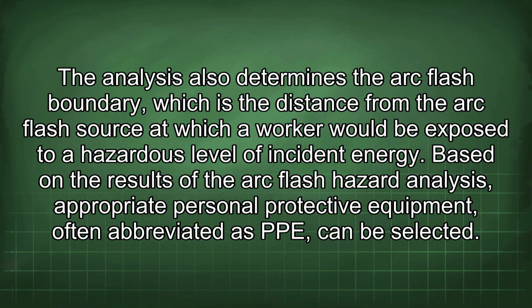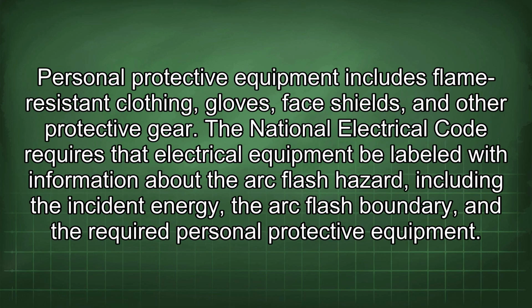The analysis also determines the arc flash boundary, which is the distance from the arc flash source at which a worker would be exposed to a hazardous level of incident energy. Based on the results of the arc flash hazard analysis, appropriate personal protective equipment, often abbreviated as PPE, can be selected. Personal protective equipment includes flame-resistant clothing, gloves, face shields, and other protective gear. The National Electrical Code requires that electrical equipment be labeled with information about the arc flash hazard, including the incident energy, the arc flash boundary, and the required personal protective equipment.